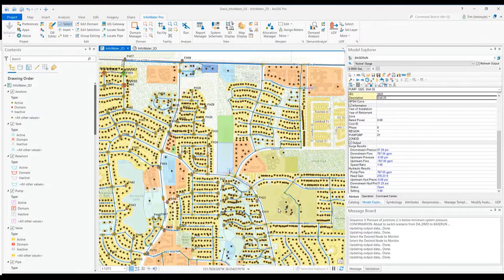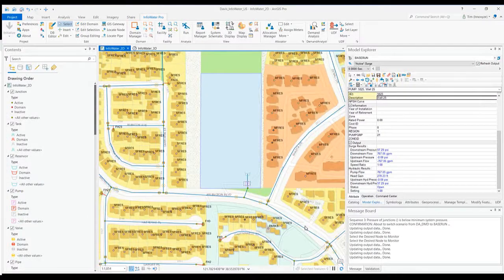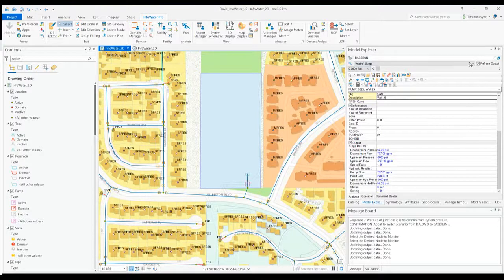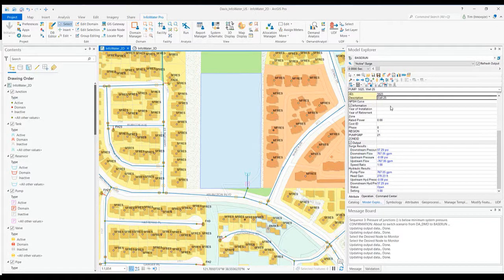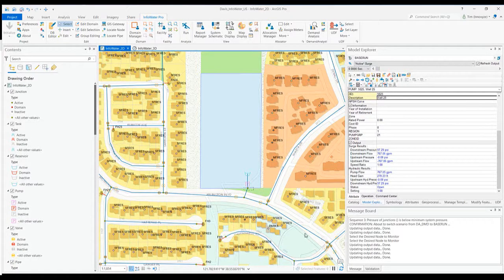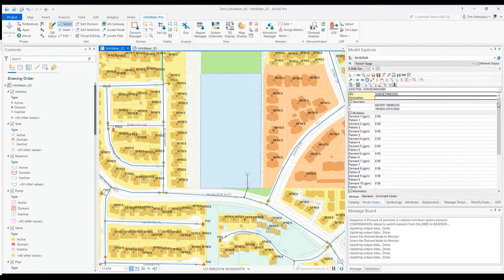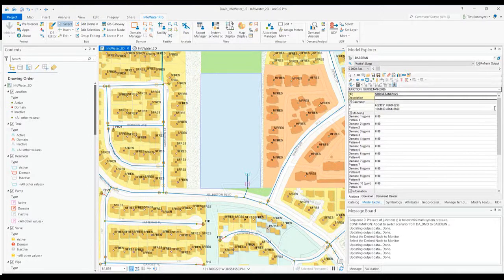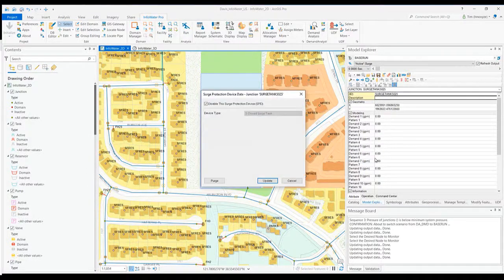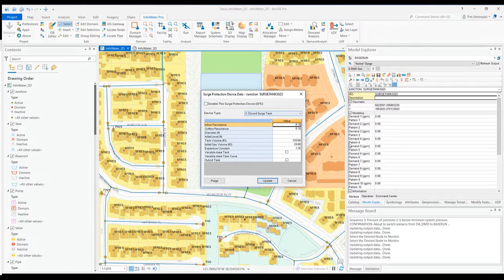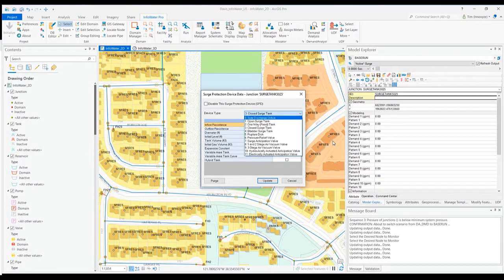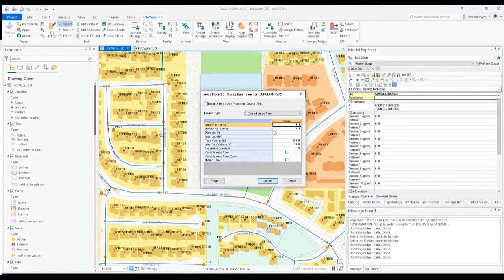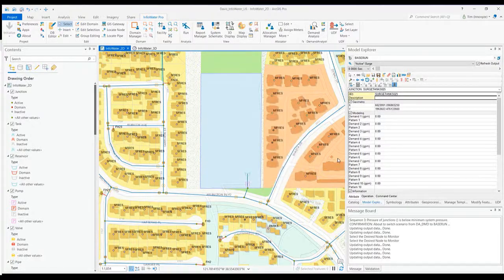I have a pump highlighted here. This is the pump that's going to be breaking, cutting off, causing that surge event. You can see I've got different controls for that. If I click on this junction, which will contain a surge tank or different surge protection devices, we're going to compare what happens without this surge protection device and what happens with it.